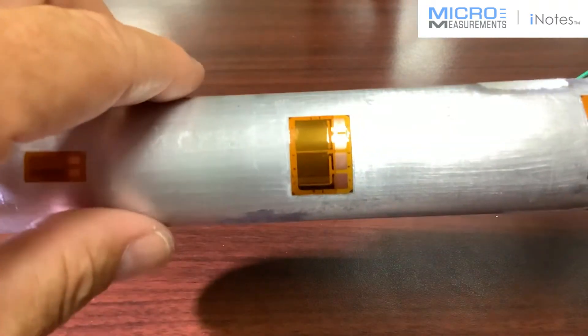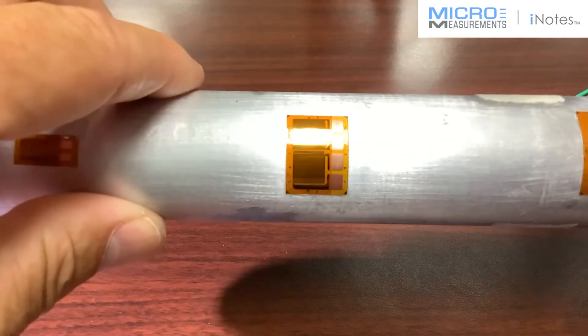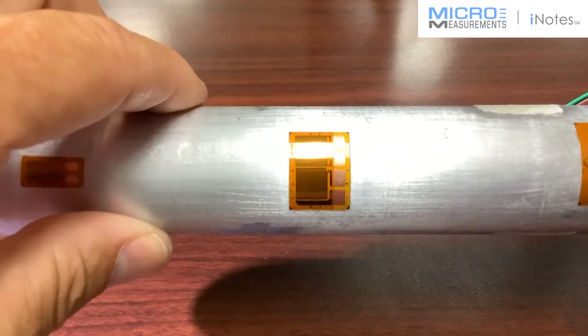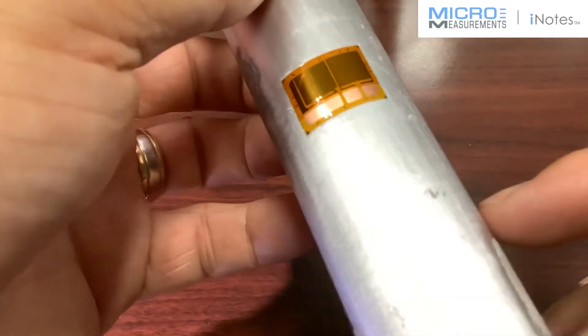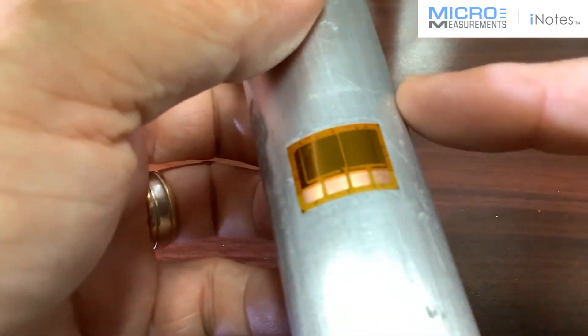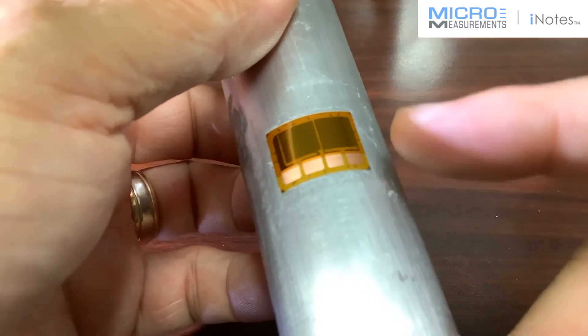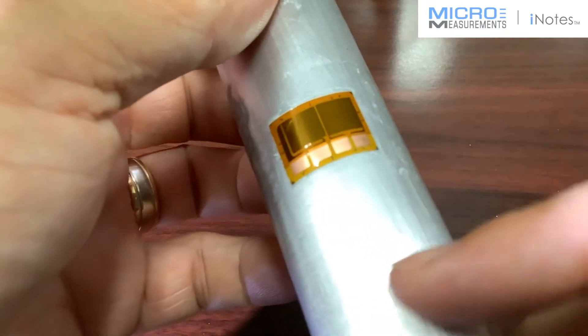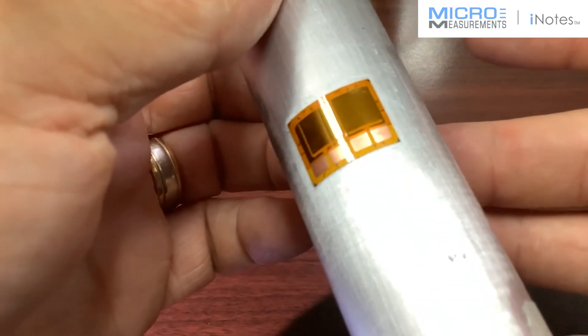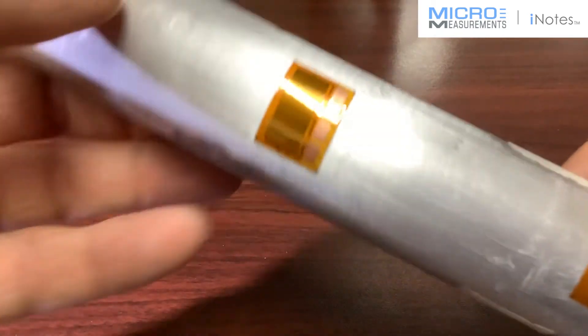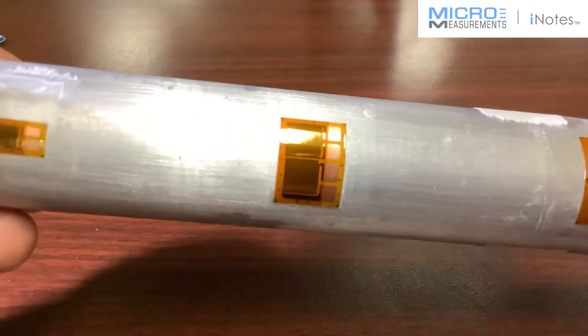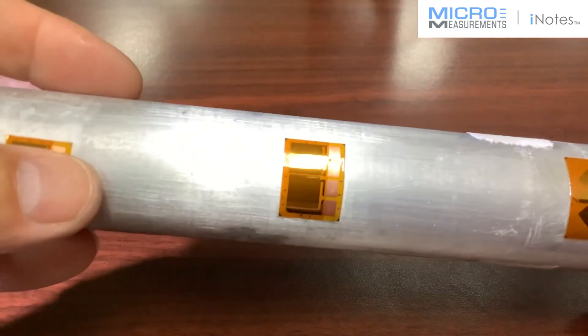You also might find that you're maybe going to measure an axial load through a tube like this, and if that's the case, you may put one of these on the front side and then put a second one on the back side and wire that into a full bridge, and then you can calibrate it for that axial load.